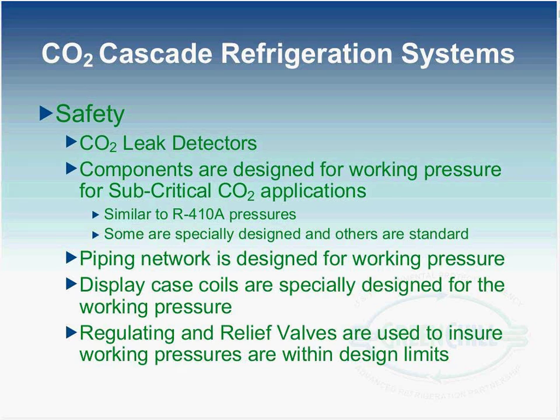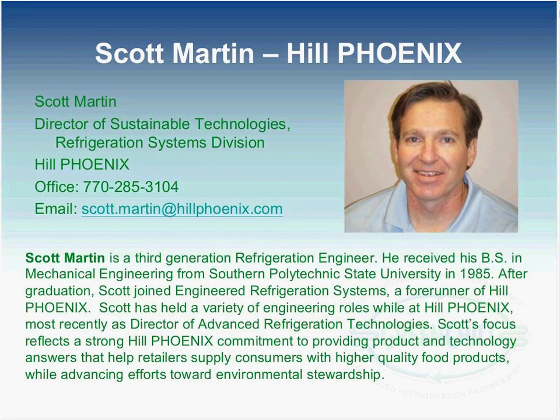There are some considerations you would need to take into account here. First off, you want to have CO2 leak detectors to make sure you can detect any leaks that are in place. Really the next three are touching on the pressure again. You have to make sure that all of the components, the piping, and the display case coils are all designed for the working pressures that you see with CO2, because you want to make sure that there's plenty of strength there to contain the refrigerant. And then you're going to want to make sure that the regulating and relief valves are used so that you can work within the pressure that the system's designed for. Basically, you want to make sure that if for any reason there is an inability to cool the CO2, there are methods in place to address that. I believe that is the entirety of my presentation.